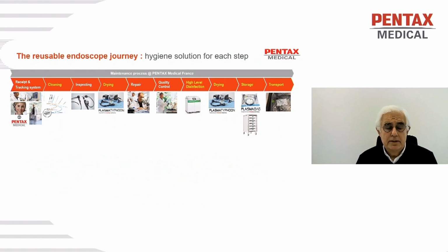Then the first thing, we're going to clean it and do the leakage test. After the leakage stage, what we're going to do is dry it. One of the good reasons is that the endoscope may have been under water. Even if it is in the contract that we repair it within 2 days, if the endoscope stays wet within those 2 days, then again, it's food for microorganisms to grow, and we're going to have some nasty surprises. And of course, if we're waiting a few weeks to get an estimate from the customer, it's even worse. So that's why drying after inspecting is very, very important for us.